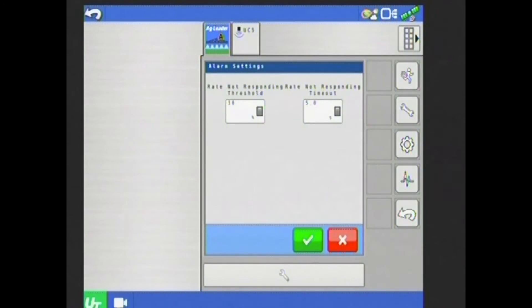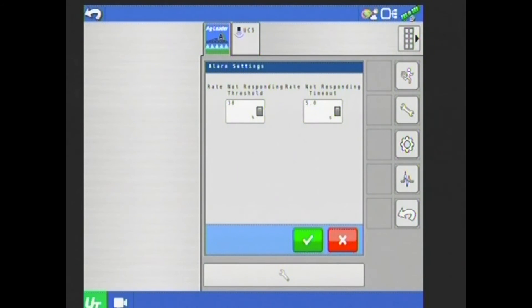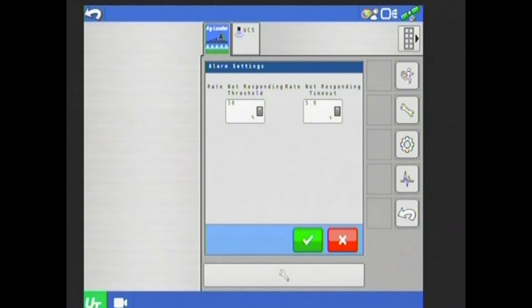Hit my double-ended wrench on the right-hand side again. Next one I have here is alarm settings, my rate not responding threshold and my timeout. 10% in five seconds are the defaults. Generally, we don't stray from those too much.